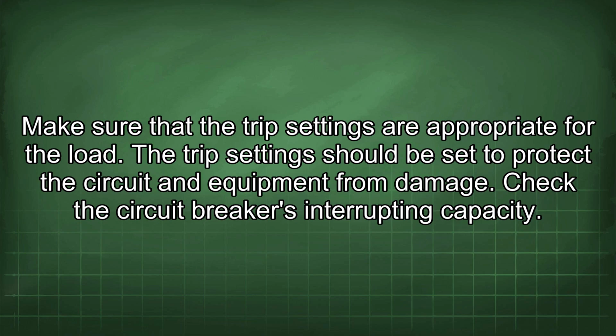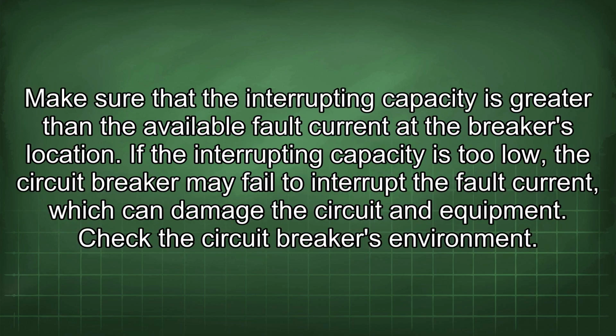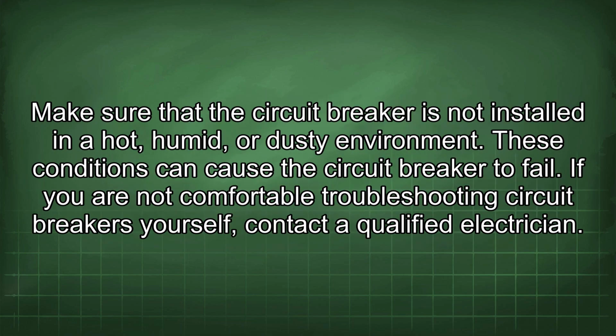Check the circuit breaker's interrupting capacity. Make sure that the interrupting capacity is greater than the available fault current at the breaker's location. If the interrupting capacity is too low, the circuit breaker may fail to interrupt the fault current, which can damage the circuit and equipment. Check the circuit breaker's environment. Make sure that the circuit breaker is not installed in a hot, humid, or dusty environment. These conditions can cause the circuit breaker to fail.